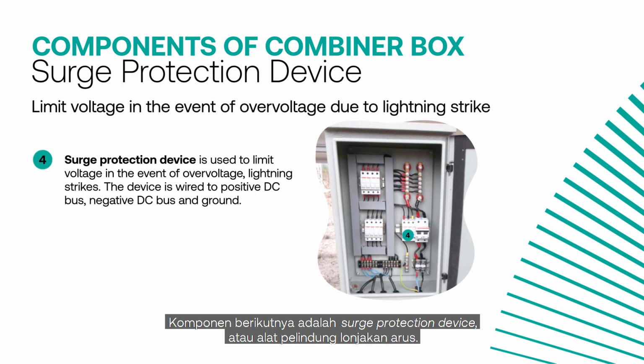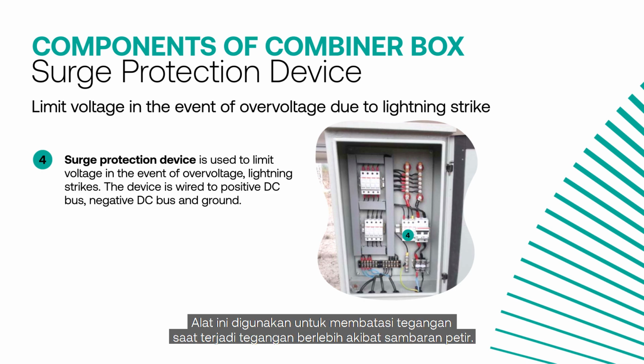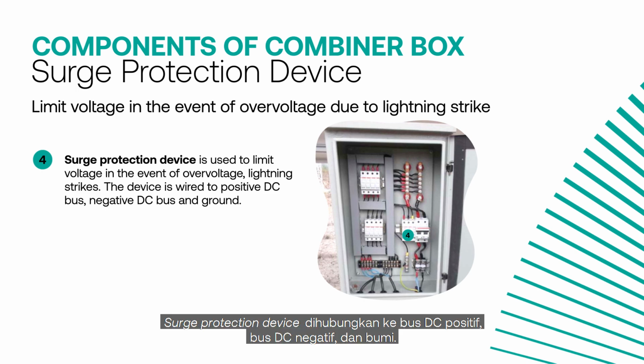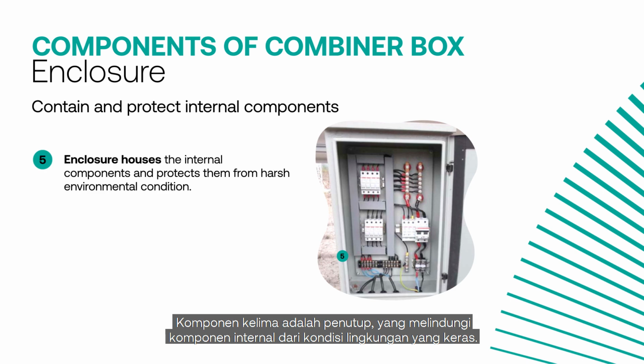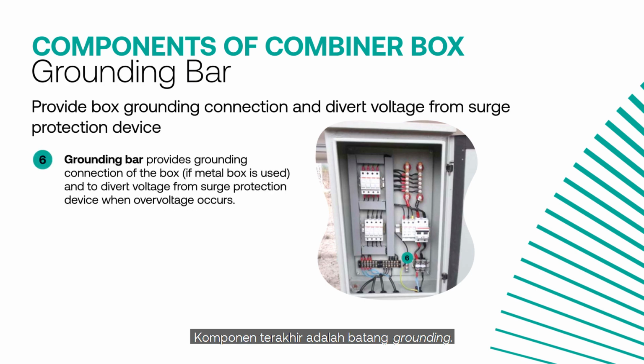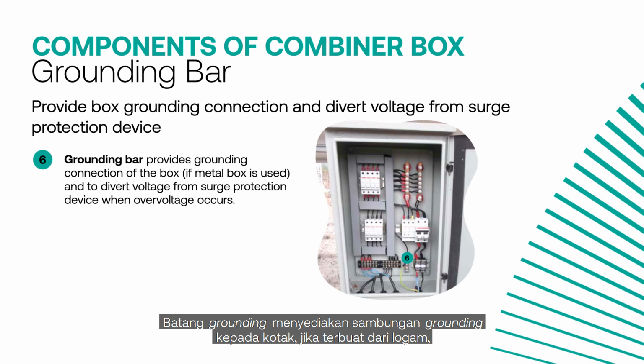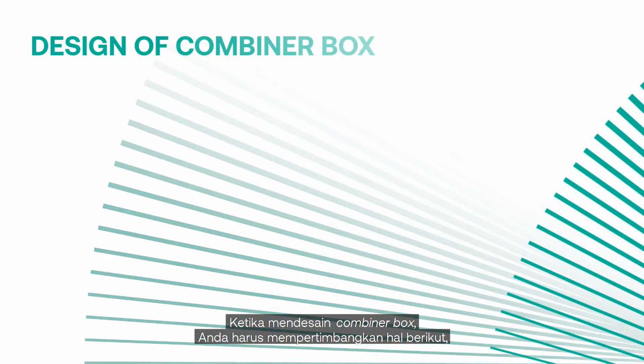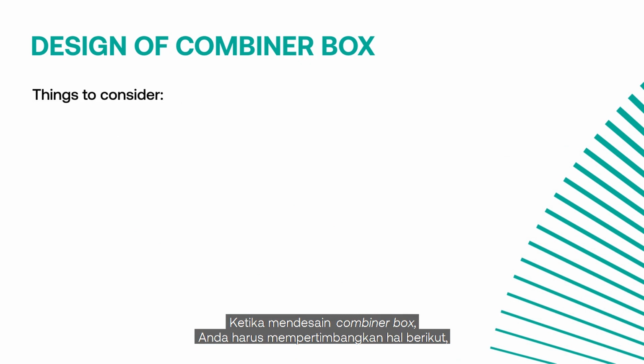The next component is the surge protection device. This device is used to limit voltage in the event of overvoltage due to lightning strike. The surge protection device is wired to the positive DC bus, negative DC bus, and ground. The fifth component is the enclosure that houses the internal components and protects them from harsh environmental conditions. The last component is the grounding bar. The grounding bar provides the grounding connection of the box, if made of metal, and diverts voltage from the surge protection device when overvoltage occurs.